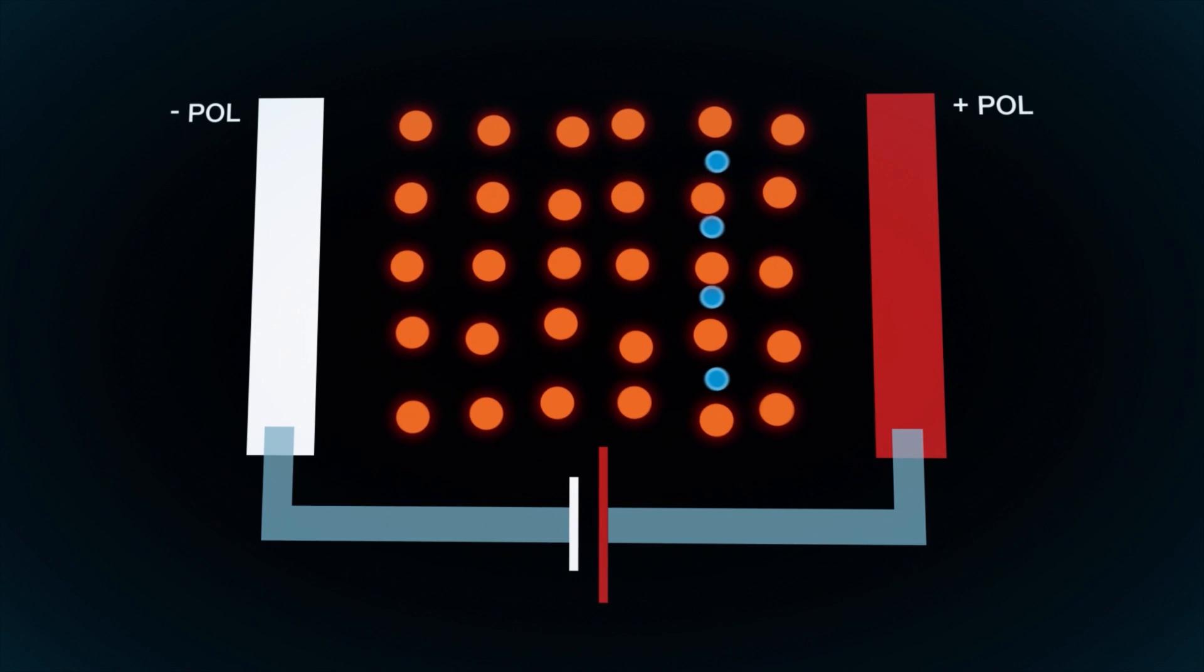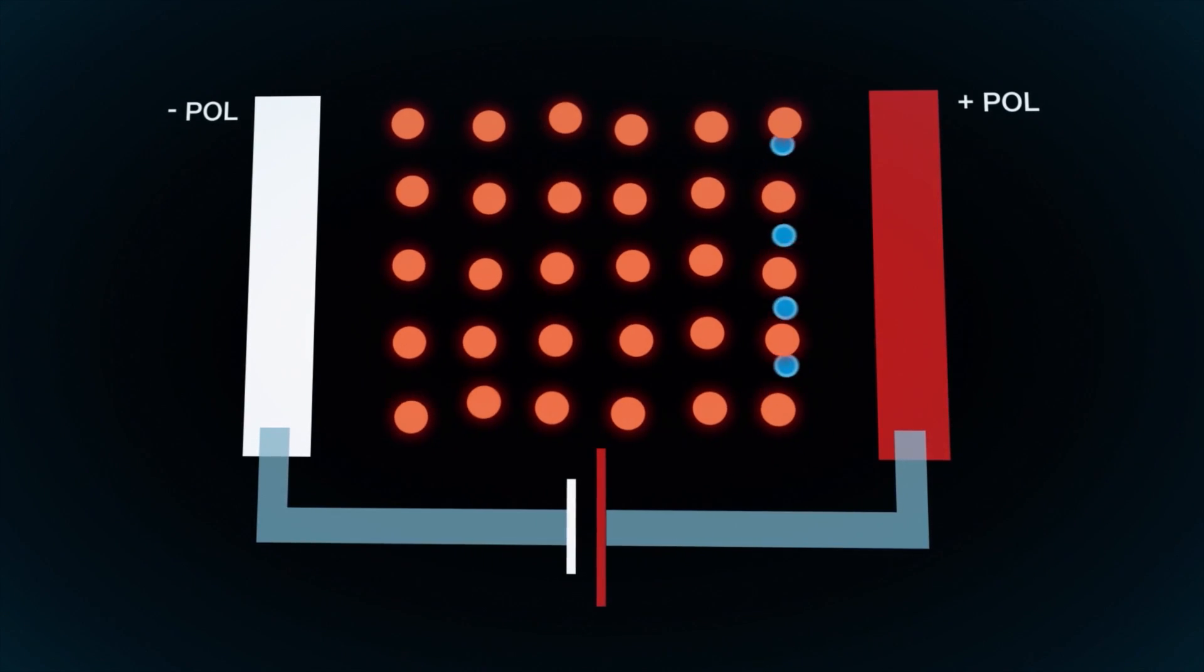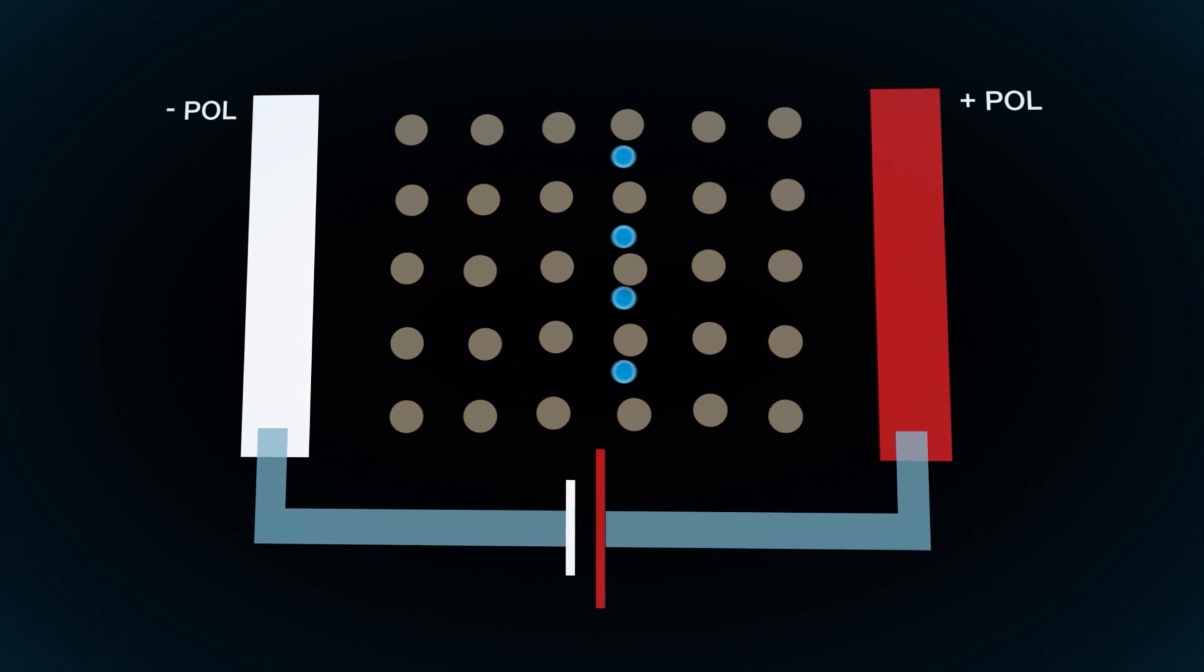A PT100 sensor has a resistance of 100 ohm exactly at 0 degrees Celsius. This value increases if the temperature rises and decreases if the temperature drops.